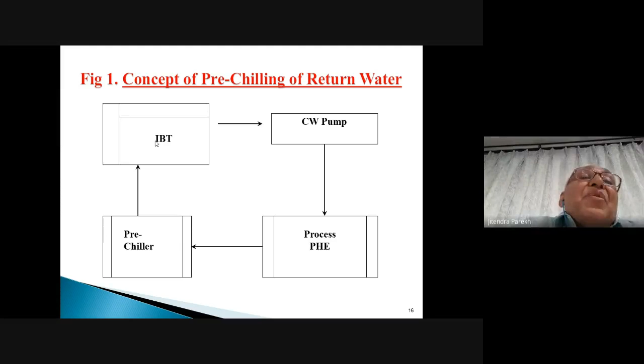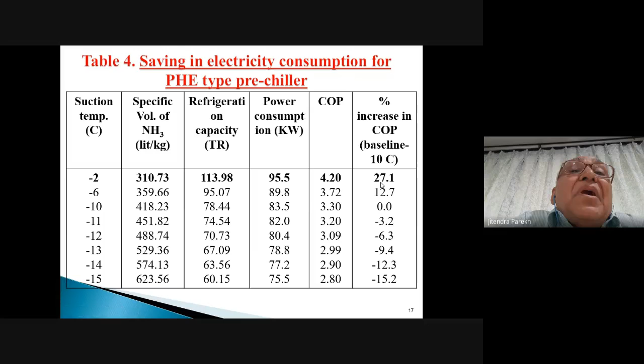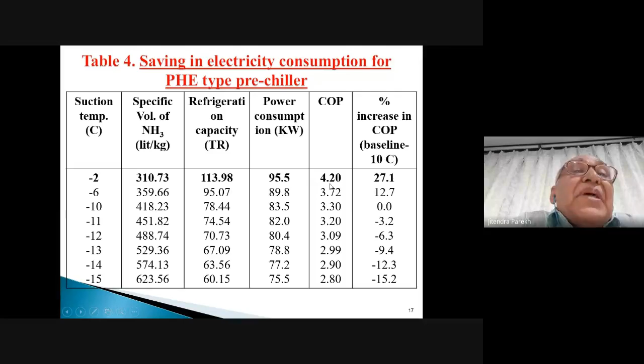Now this is what I have tried to show, how much the PHE type of pre-chiller helps in consumption when you have a suction temperature of -2. If you see on the right side, the increase in COP is 27.1%. The other parameters are the same. So there are a lot of advantages when you use the PHE type of pre-chiller. The load will go down and the COP of the machine compressor will also be improved a lot. Next, please.